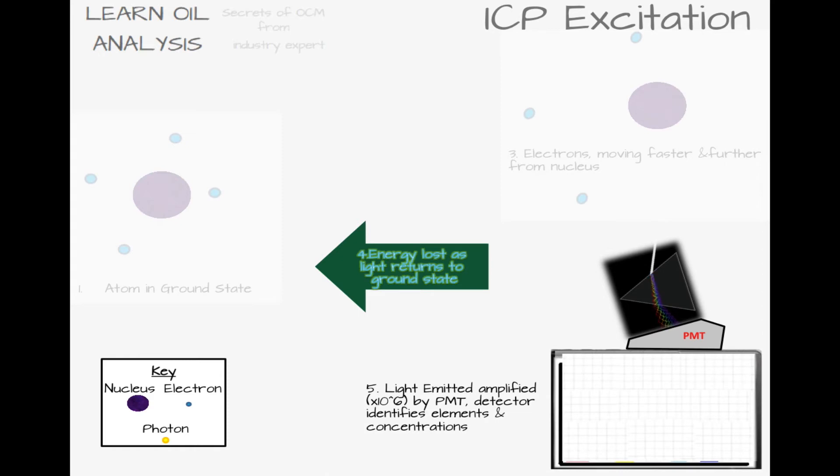The atom is now returning to the ground state and its photon, combined with the other atom photons, coloured yellow, go through a diffraction grating, similar to a prism, to split the light into their individual wavelengths. These photons reach a photomultiplier tube, or PMT, which enhances the signal up to a million-fold as an electrical signal, so it can be detected.